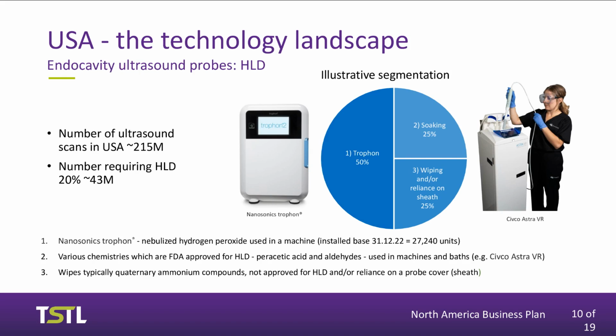The other 2 methods, and let me describe it, is the picture is on the left-hand side. It's a box. It's a machine controlled by a microprocessor, powered by electricity. The disinfectant chemistry that's used inside the box is hydrogen peroxide, which they make into a vapor, which surrounds the ultrasound probe. It has a contact time of 7 minutes.